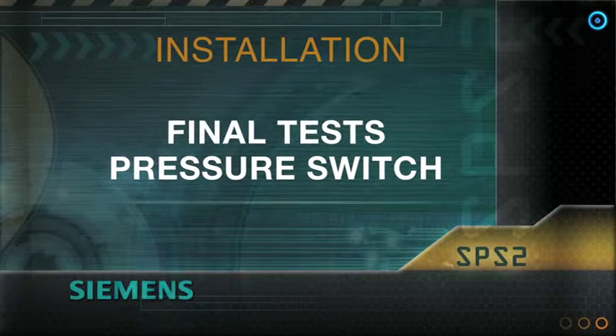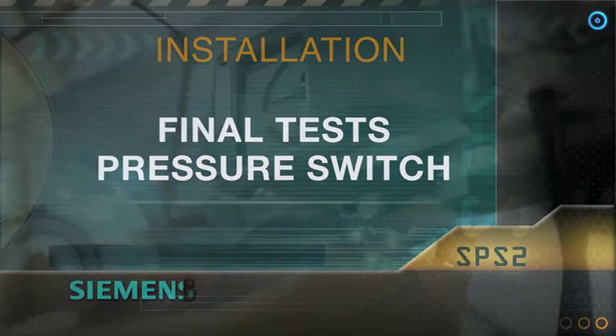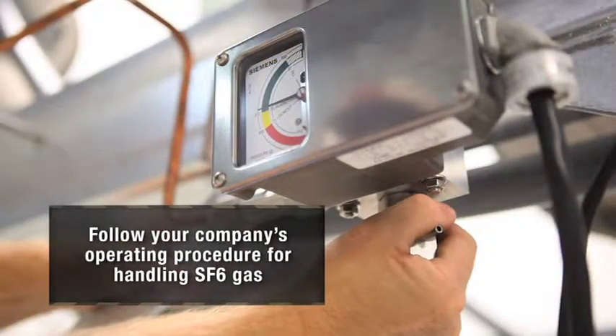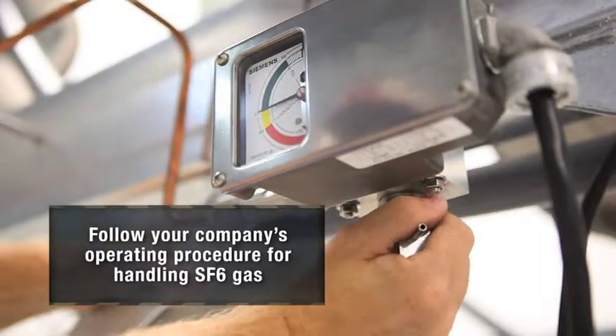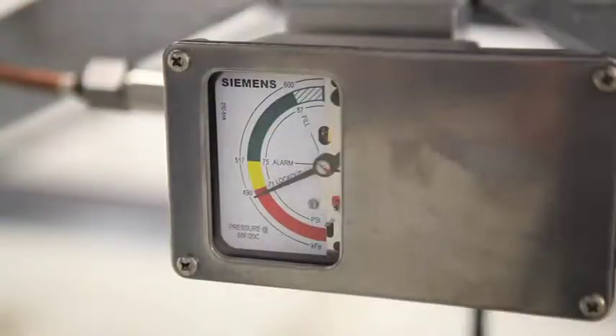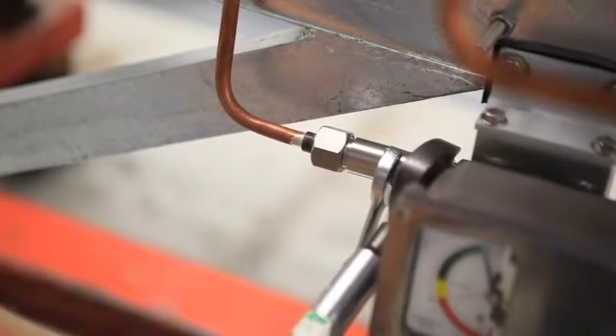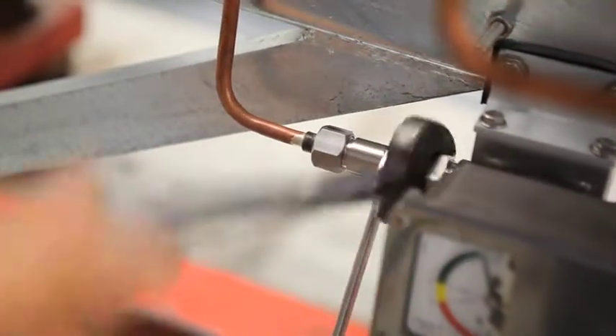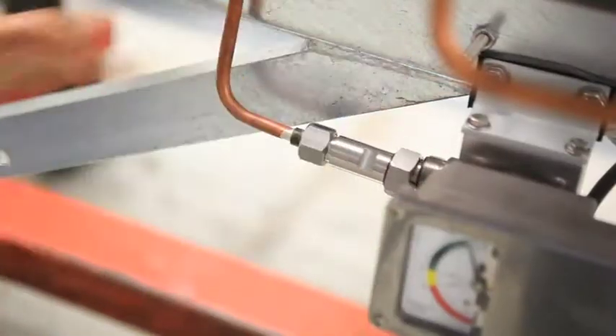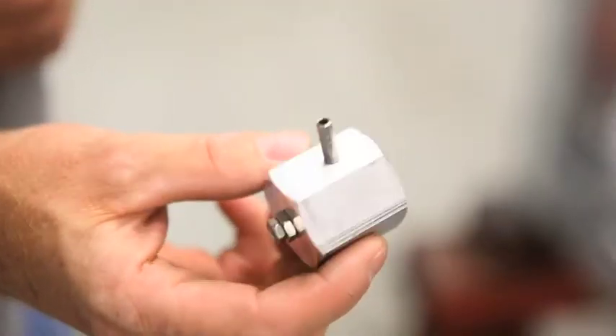Installation. Final tests, pressure switch. Verify the alarm and cutout pressures of the temperature-compensated pressure switch. The contacts operate on falling pressure. Isolate the pole units by closing the shutoff valve and connect a continuity device to cross each contact in turn. Attach the bleeder valve that shipped in your breaker kit.